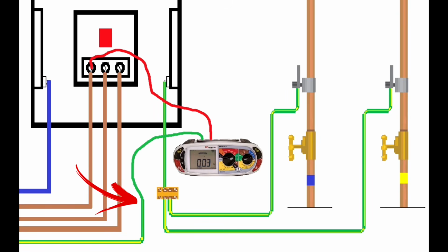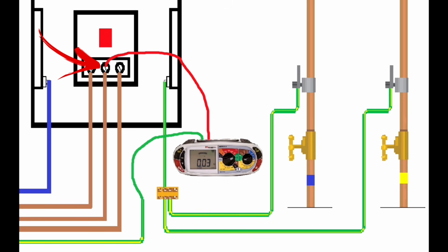I've connected onto my disconnected earthing conductor an L1, and I would perform my earth fault loop impedance test and remember the reading. I would then move it on to L2 and repeat the test again. Remember, this is at the bottom of the main switch with the board isolated, so it's the only live part within the board. And I would remember that reading. So I would test between the earthing conductor, L2, as an external earth fault loop impedance, remember the reading, before I move on and test L3. L3 now, my disconnected earthing conductor are tested, and I remember the highest of those three readings, and the highest reading would be recorded as my ZE value, my external earth fault loop impedance of this distribution board.